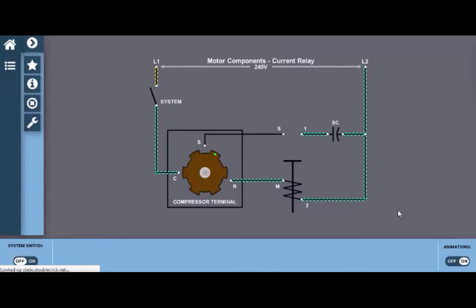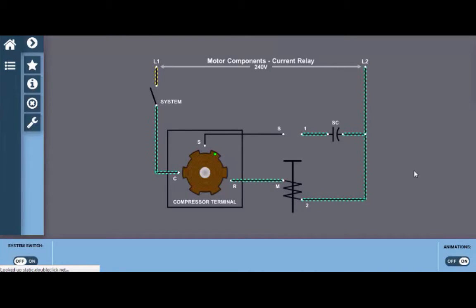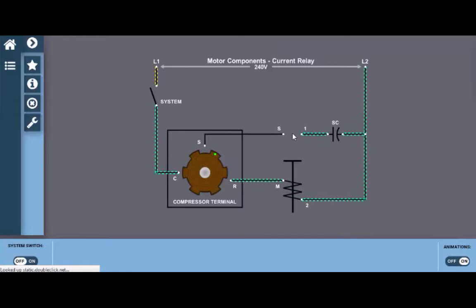the coil, which is located between terminals 2 and M shown here, will de-energize due to the decreased amperage as the motor speeds up. Once the amperage has been decreased, the contacts in the current relay will open and break power to the start winding.